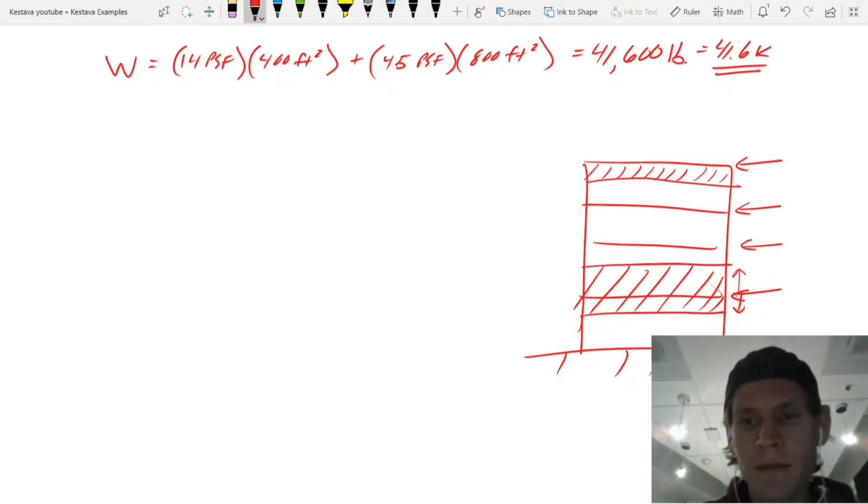And then same thing at the bottom, at the bottom, you just move directly to the base. So overall, your total seismic mass is the whole building, because that sums up as base shear at the bottom. But in terms of overturning design and stuff like that, and lateral design, design of your diaphragms, the seismic mass is split up, like I said, half story below and half story above, when you're finding all your surfaces and stuff. So that's the one little trick here.